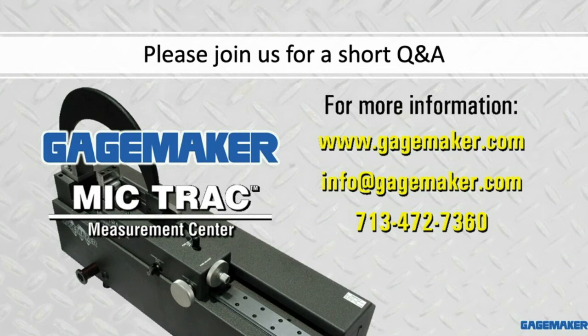Yep. Depending on the size of the linear measurement device, the MIC TRAC, ours start at 12 inches as the smallest, and typically a catalog one goes all the way up to 60 inches, but we've done longer than that. The longer they are, the more expensive they are, and there's typically some cost associated with the amount of time that you're not going to have the unit. It has to come to us because it's very sensitive. It has to, we call it soak and get to temperature. So you're looking in the hundreds of dollars to calibrate one of these on those typical intervals, and usually it's once a year. But it could get up close to under $1,000 for the highest accuracy and the longest scale. So in the hundreds of dollars typically per year.